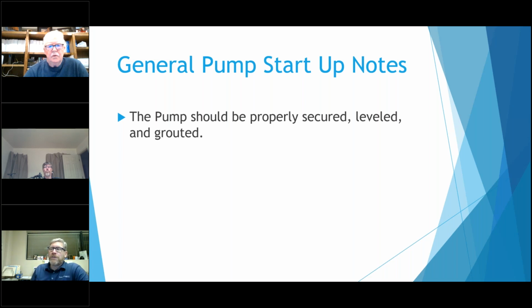So they said, okay, we'll do it, and they went ahead and did it. Now when I went back, you actually had to get right next to the pump to feel the vibration in the floor, where before you felt it as you walked into the room. So if you've got a pump, especially a base mounted pump, that's vibrating, it's a good idea to grout it. Again, you may not get rid of it because you could have other issues causing the vibration, but it's certainly going to help get rid of some of that vibration.